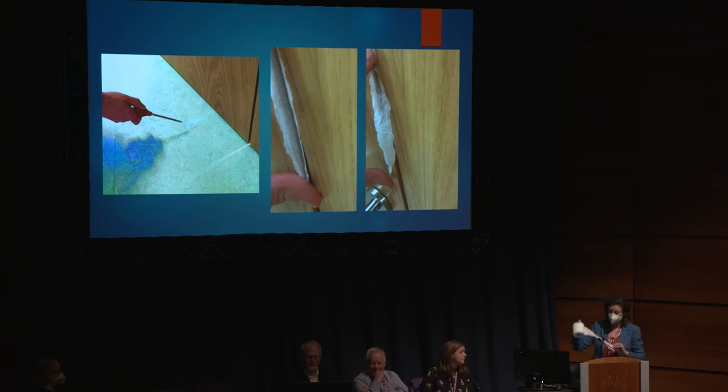That's where the toilet paper comes in handy. This is the reverse: an allegedly negative pressure room - put the toilet paper there and it comes blowing out. That is not a negative pressure room. In our CL3 laboratory, for biosafety we have cabinets to make sure the air is taking anything away, and we need a visible display of where the air is going. Over the centuries we've realized that dials and the best laid plans of mice and men can go wrong, and what you need is something visible telling you which way the air is going.